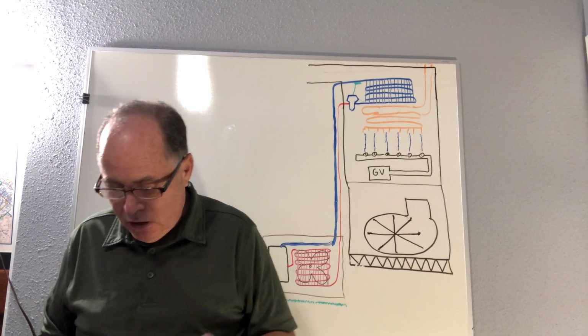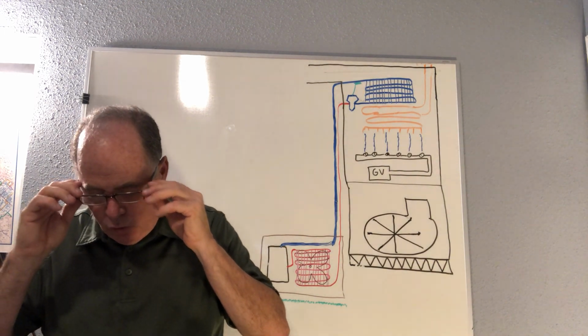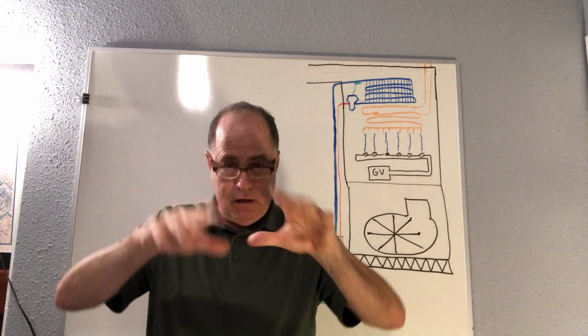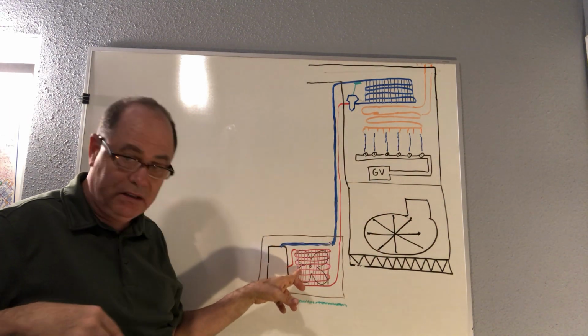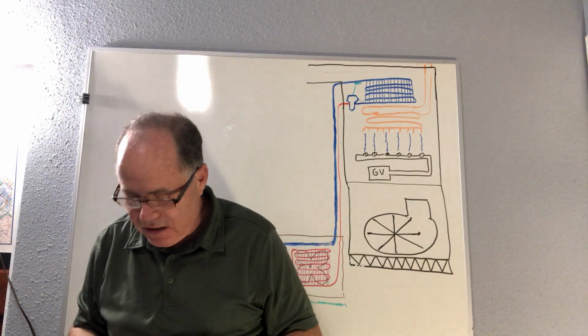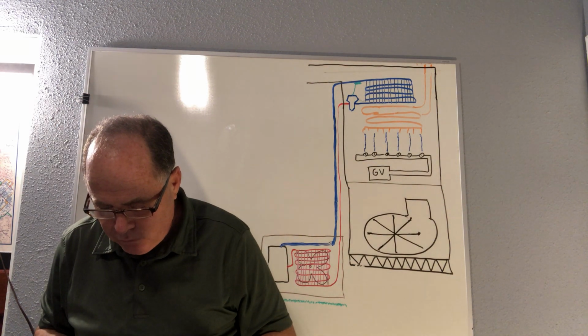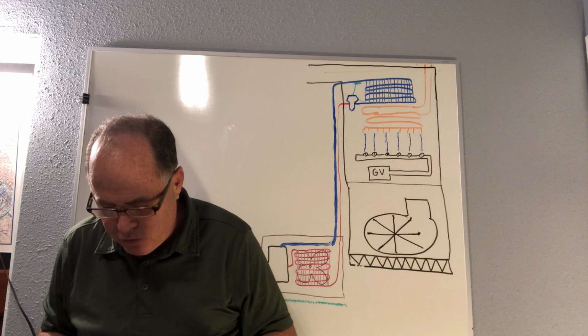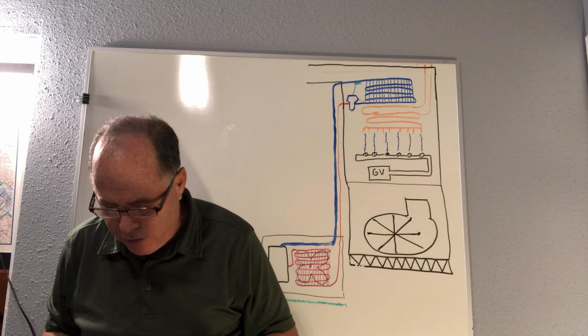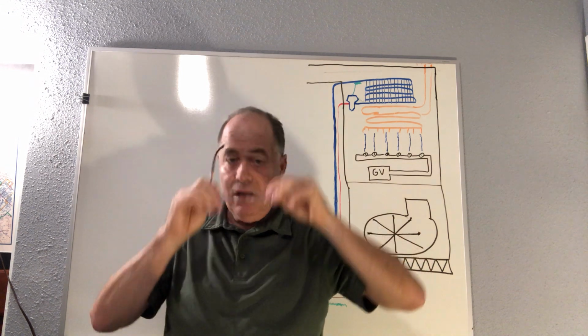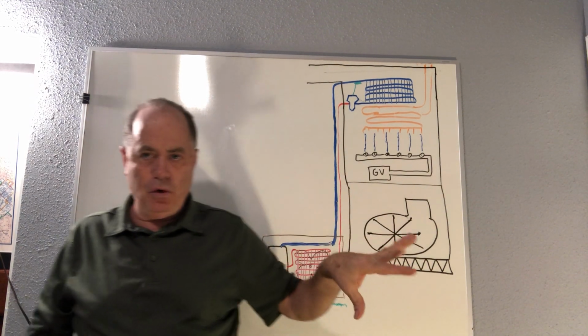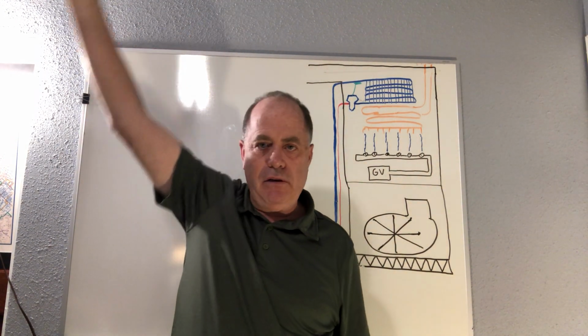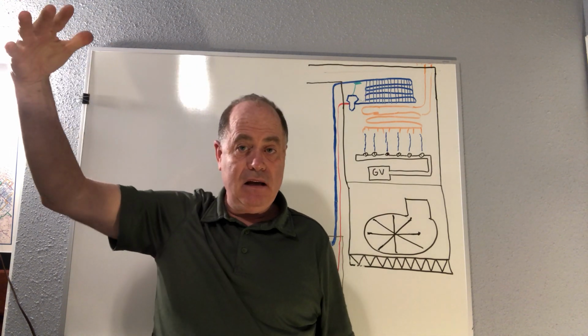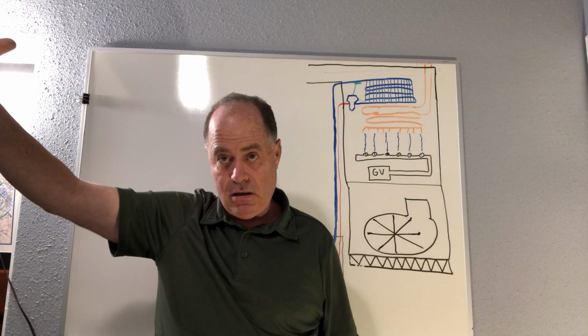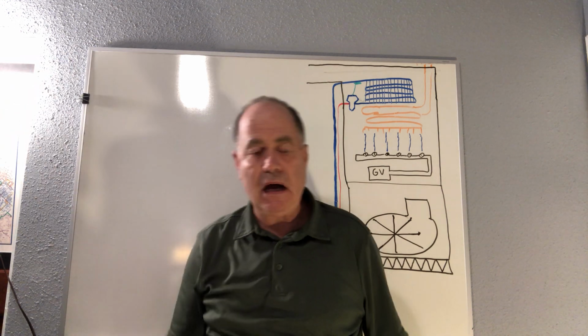Also, refrigerators, talking about old school refrigerators, with that grill on the back, but no fan, just a big static grill. It's called a static condenser. It says not less than 2 inches between the back of the refrigerator and the wall, and 12 inches above the top. Now, generally, that's super old school thinking, and we want to have airflow all around the refrigerator to dissipate the condenser heat from these old school type refrigerators.